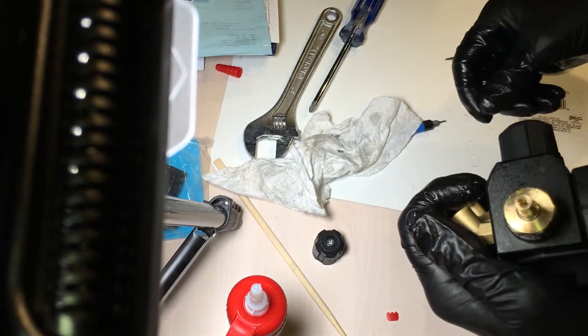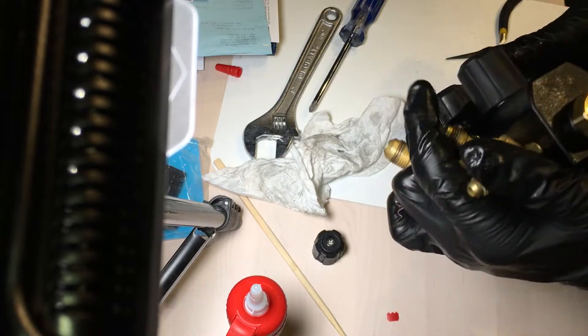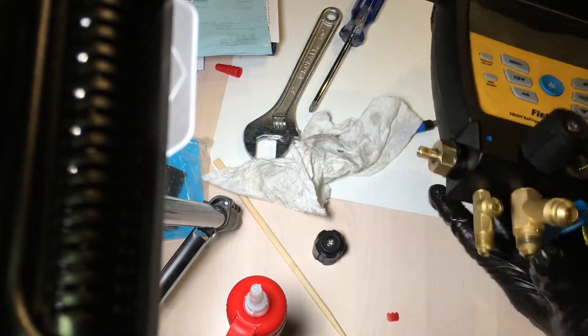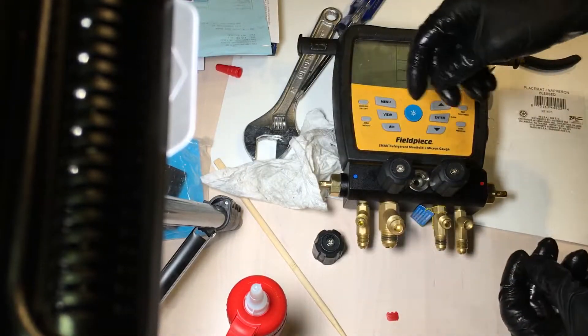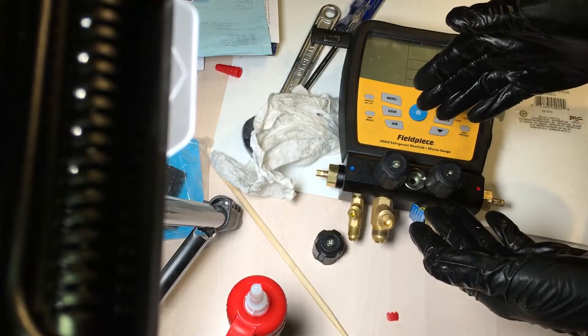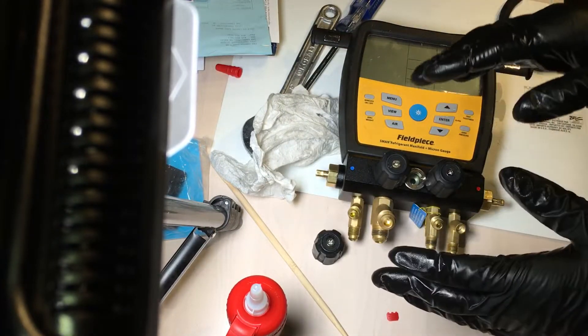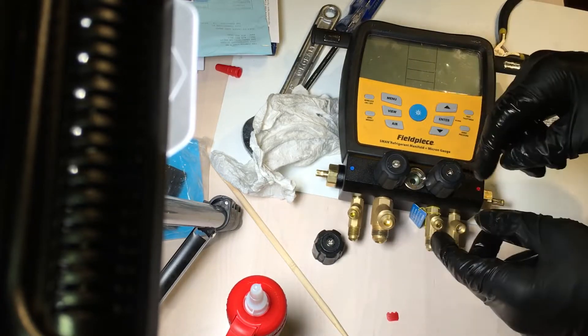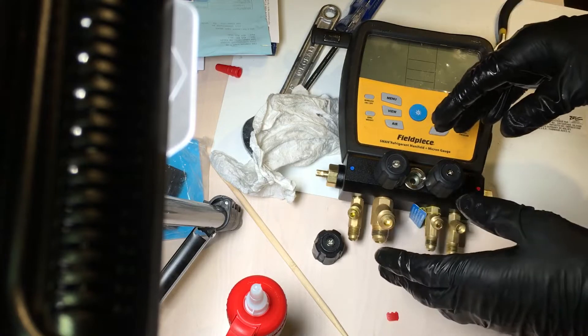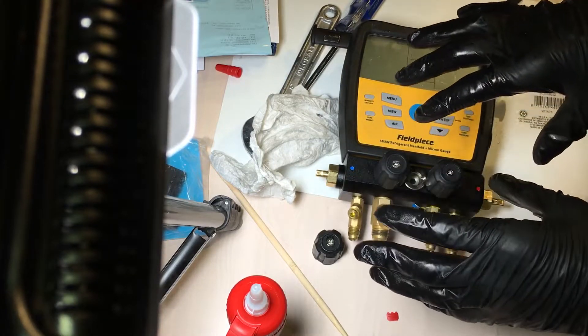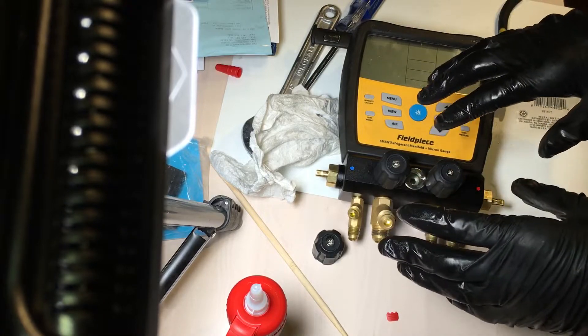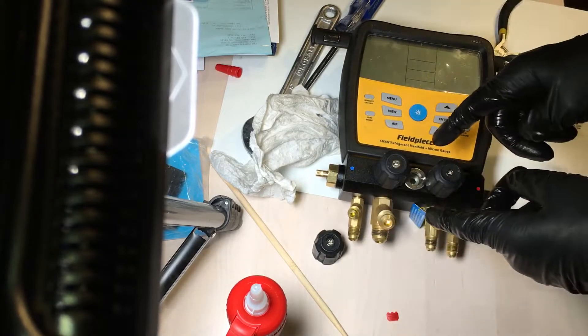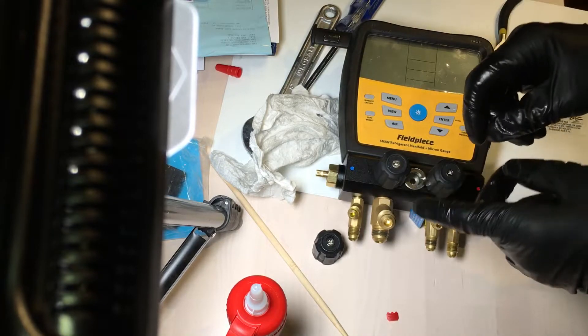And that's it, that's how simple this is. You will have a new set of o-rings for sealing. If you did have a problem with performing a high pressure nitrogen decay test or a vacuum decay test, what you're not supposed to do is a deep vacuum long-term decay test through refrigerant hoses and a manifold in the first place.